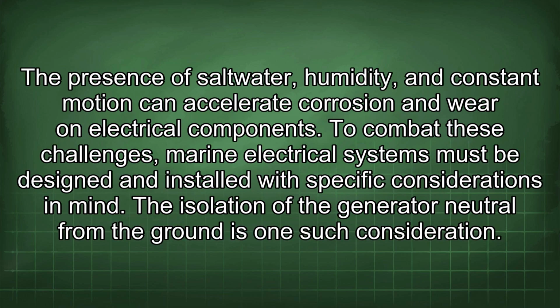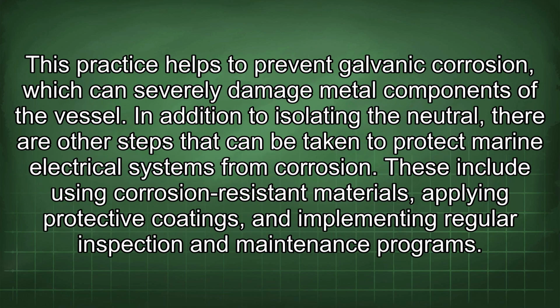The presence of saltwater, humidity, and constant motion can accelerate corrosion and wear on electrical components. To combat these challenges, marine electrical systems must be designed and installed with specific considerations in mind. The isolation of the generator neutral from the ground is one such consideration. This practice helps to prevent galvanic corrosion, which can severely damage metal components of the vessel.